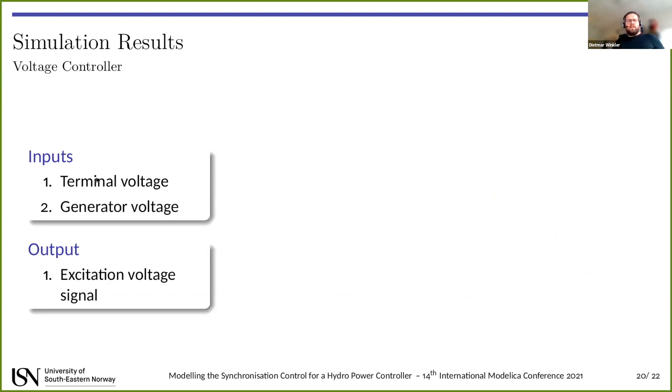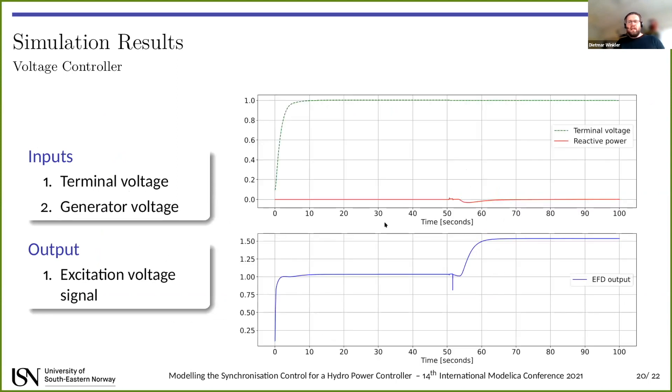Last thing, voltage controller. It has two inputs, the terminal voltage and the generator voltage. Then the output is the excitation voltage. Here you can see during the synchronization, the output is set to slightly above one in order to keep the terminal voltage as it should be. Once we're connected, it's now producing active power, which means the machine internally uses reactive power, which then the voltage controller tries to compensate in order to run power factor one. So you see here the output of the voltage controller is ramping up in order to provide enough reactive power for the active power production.